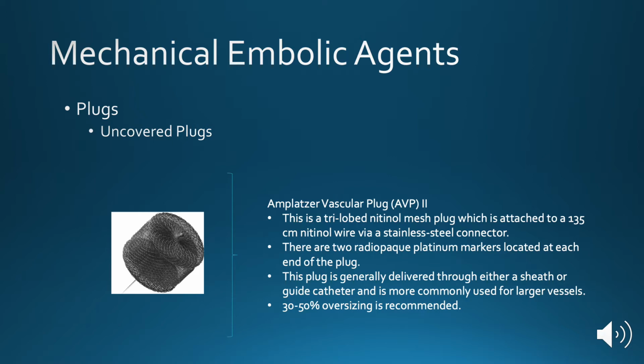This is the AVP2, which is a tri-lobed nitinol mesh plug, which is attached to a 135 centimeter nitinol wire via a stainless steel connector. There are two radio-opaque platinum markers located at each end of the plug, and this plug is generally delivered through either a sheath or guide catheter and is more commonly used for larger vessels. When deploying these plugs, 30 to 50% oversizing is recommended.